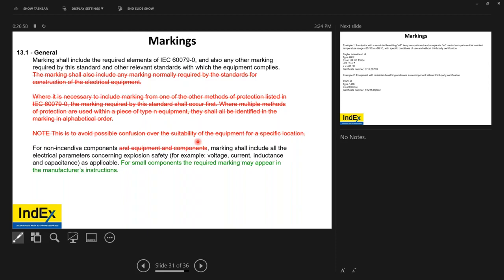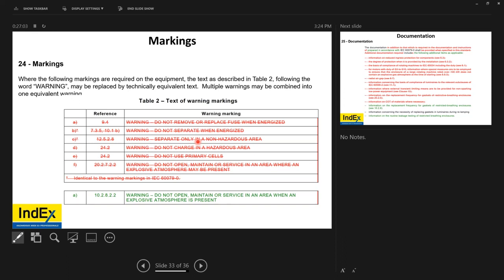So warnings. Well, it was under 24, but all these things marked in red. Look at all these different warnings you had to have depending on which clause reference you were going from. Were you at 9.4? Well, then you better have a warning for don't remove the fuse. We're at 7.3.5 or 10.1, warning, do not separate when energized. I would guess that would be maybe EXNL or something left over. 12.5.2.8, separate only in non-hazardous areas. 24.2, do not charge in hazardous area. That's probably batteries. 24.2, do not use primary cells. Yep, batteries.